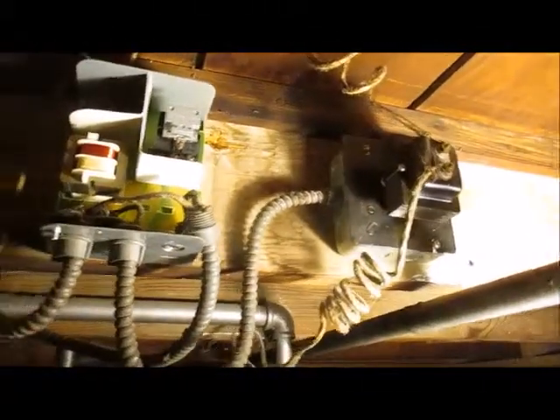Now, if your whole system's on, you hear it running, but the gas didn't open up, then more likely it's your gas valve, and then you troubleshoot that all the way back to the switch relay. But don't use your fingers. Don't use just a wire hanger or anything. I mean, get a circuit tester. Like I said, I had the little cheapy $7.99 one. I'll go ahead and show you. I'm sorry, I'm a little bit tired and under the weather showing you this, but I just felt that I needed to show people how, if they have their own hot water boiler.